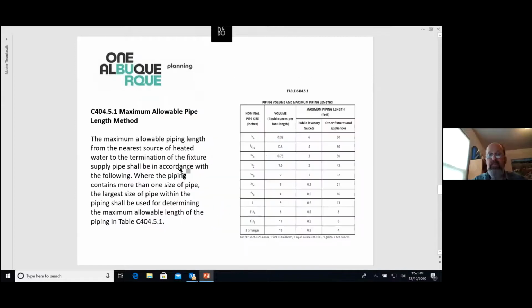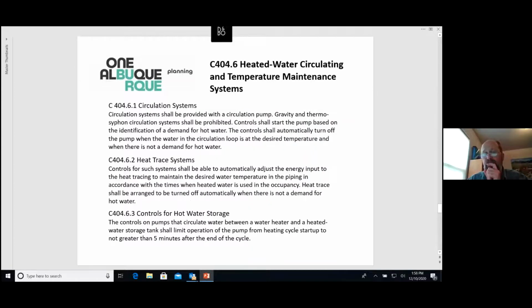So back to the chart, it shows you a 1/2-inch line, the maximum amount of 1/2-inch pipe you can have off of the main, in essence, is 2 feet. Typically, we would run it down a wall 6-7 feet to stub out below the cabinet or below the lavatory. You can't do that anymore. So that's what that is. Any questions on that? Okay.